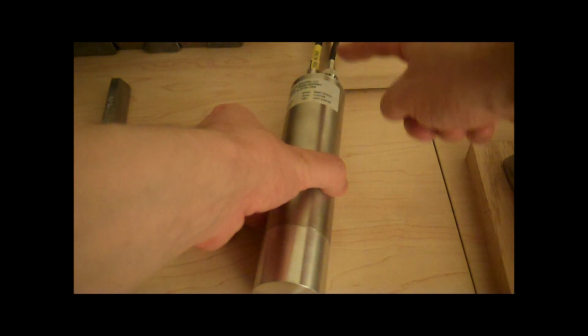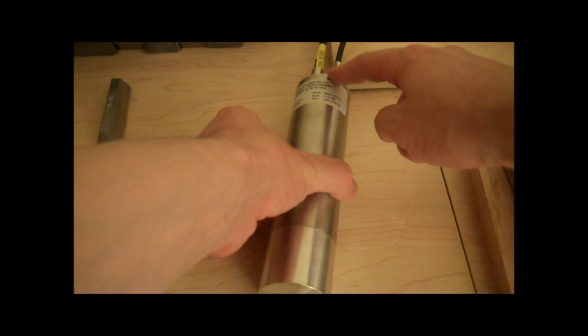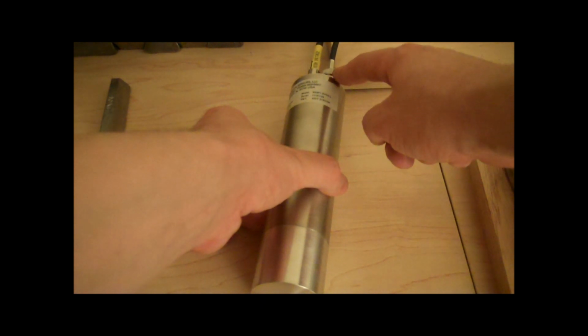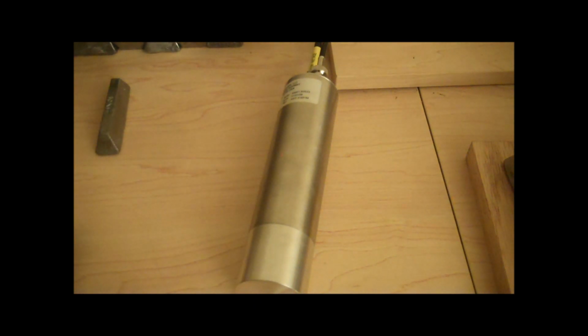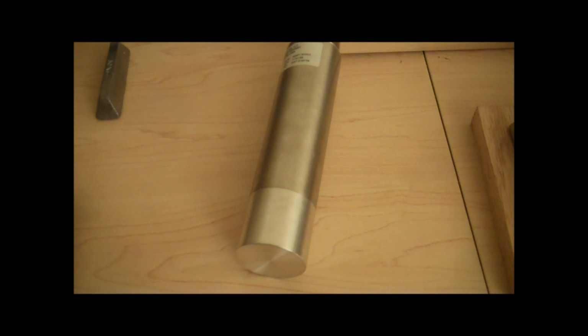In the back, power comes in, high voltage. And on the other side of the back, a signal, a pulse leaves. Now, in the front here is a sodium iodide crystal. It has been doped with thallium. This crystal reacts in a very peculiar way when gamma or X-ray radiation strikes it. When a high-energy photon, such as gamma or an X-ray, strikes this crystal, it produces a flash of ultraviolet light.